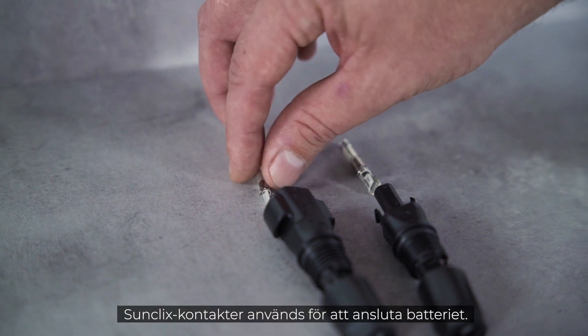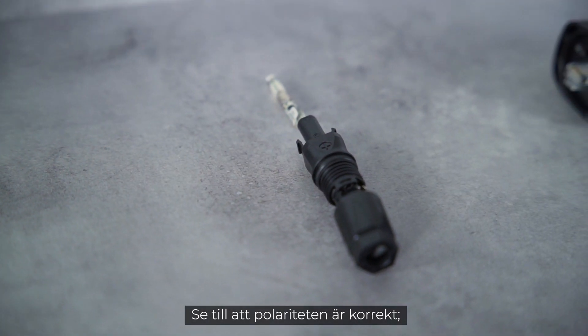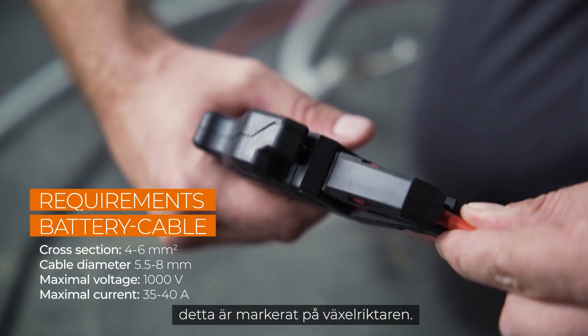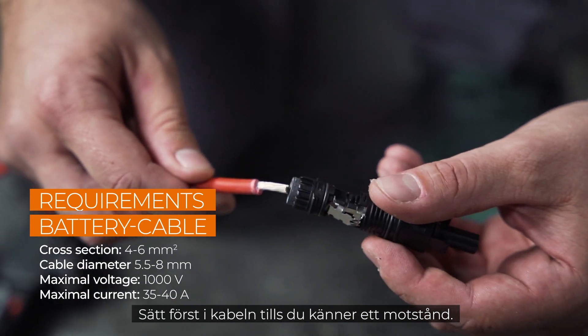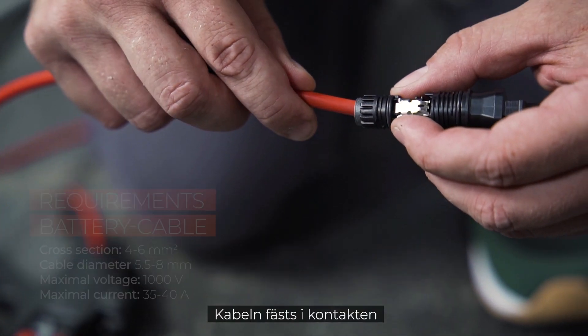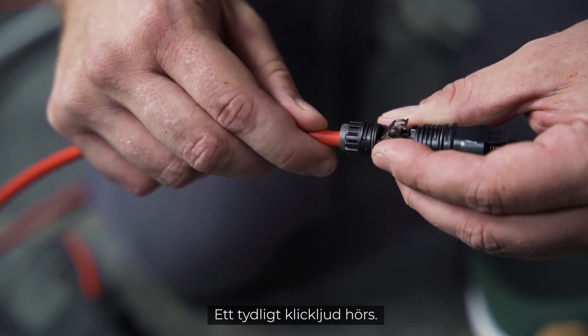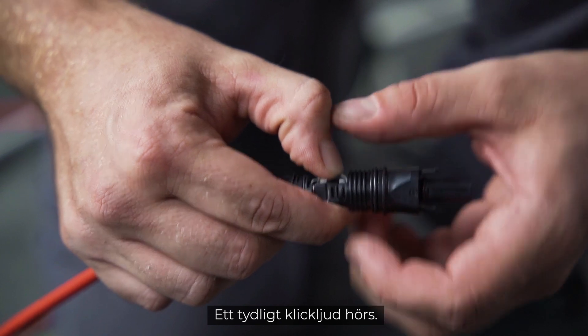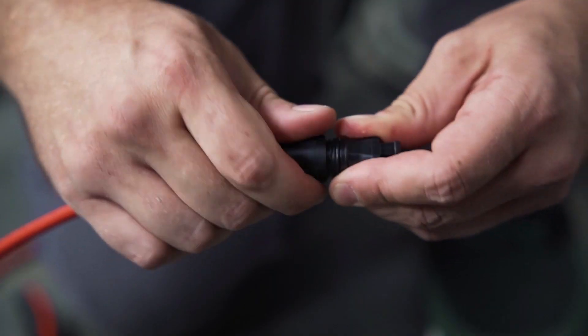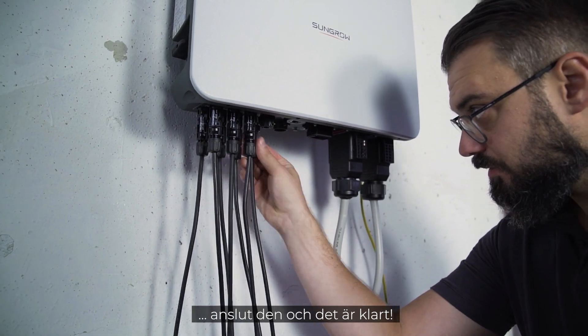Sunclix connectors are used to connect the battery. Pay attention to the correct polarity, which is marked on the inverter. First insert the cable until resistance is felt — now the cable is fixed to the connector by pushing down the spring. A clear click can be heard when it clicks into place. Tighten the plug, plug it in, and that's it.